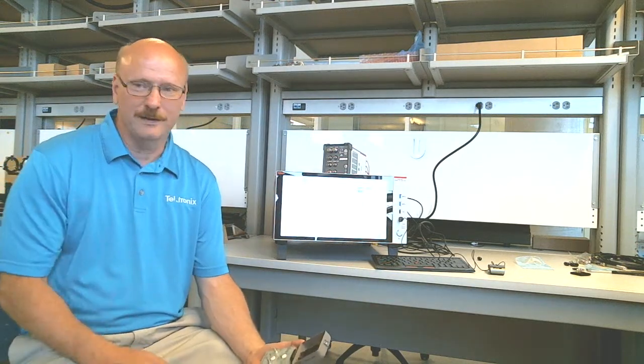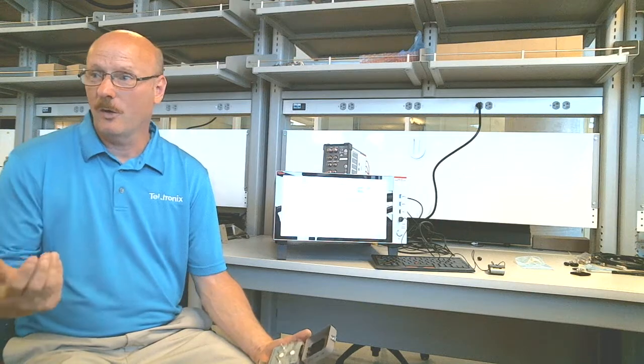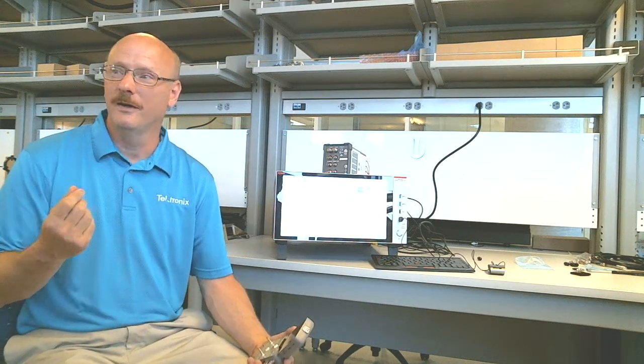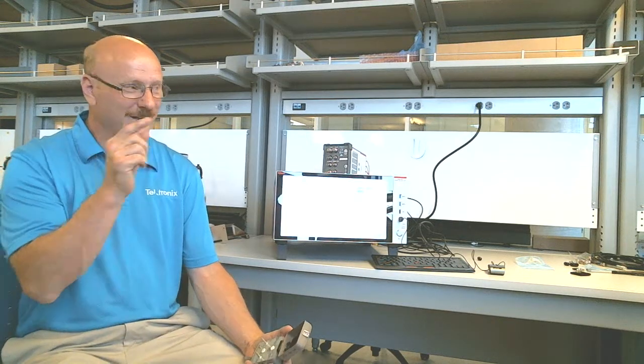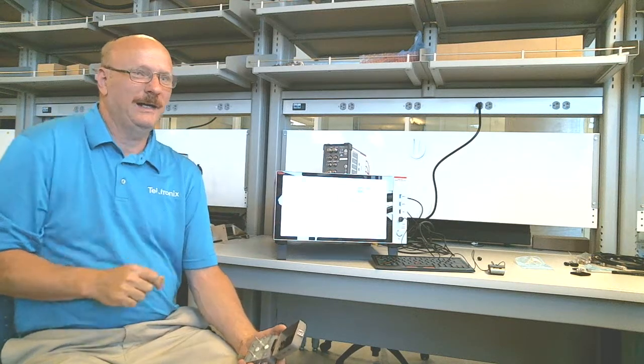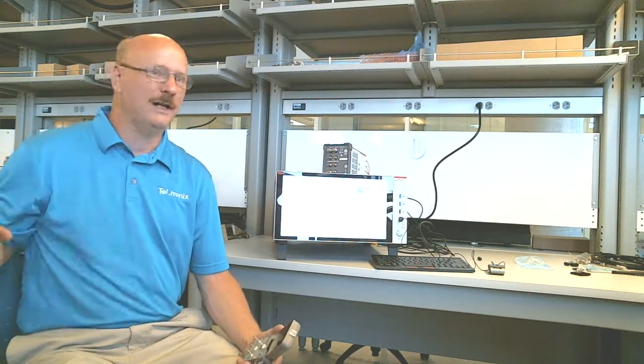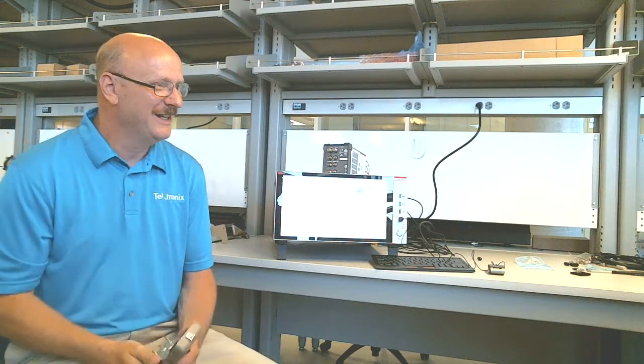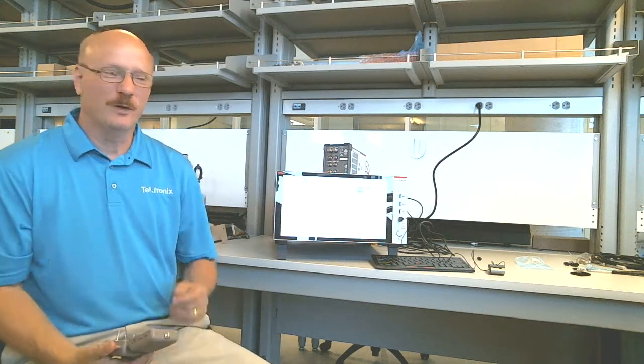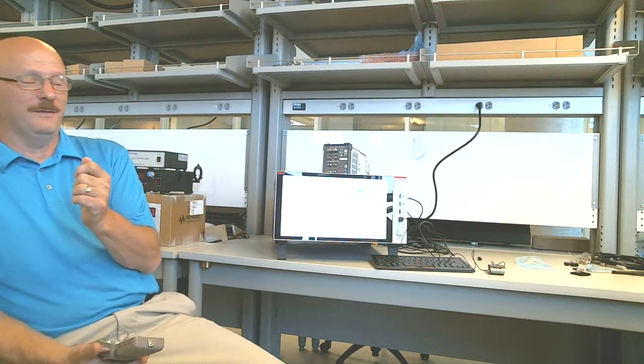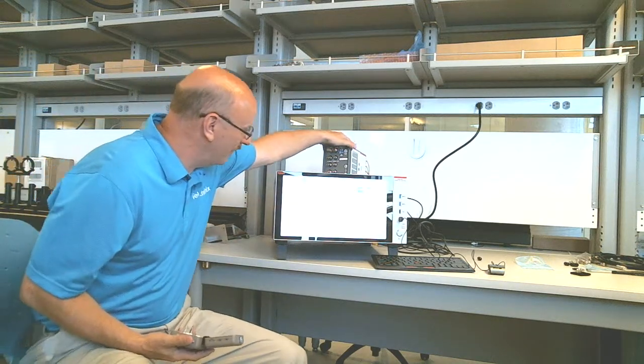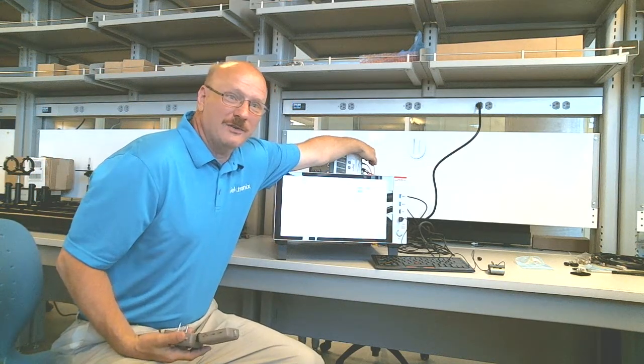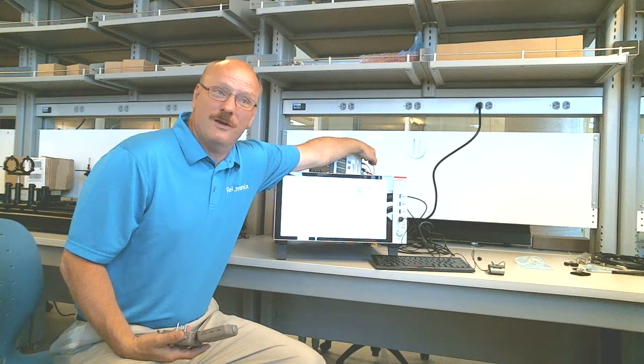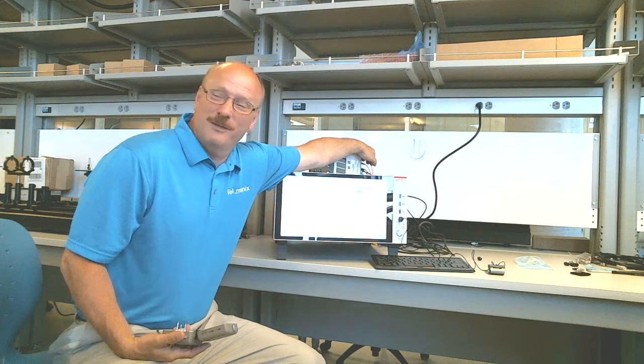The difference is that AC is done via coax, not triax, so you have to deal with the shields. The shield is your return, so you have to short the shields together, and you're going to have to do that over there. I'm telling you this now, but you're still not going to do it because nobody does—you're going to forget about it. When you do CV measurements, it's an AC measurement, going through the red coaxial cables where the outer shell is your return. You have to do something with that return.